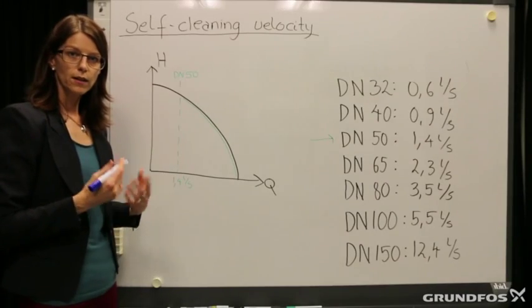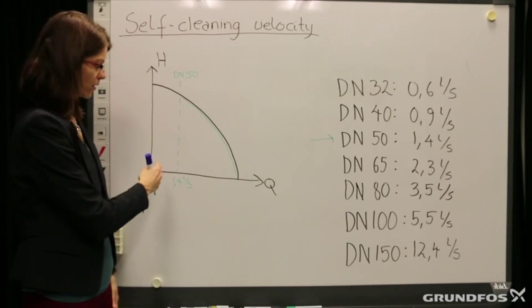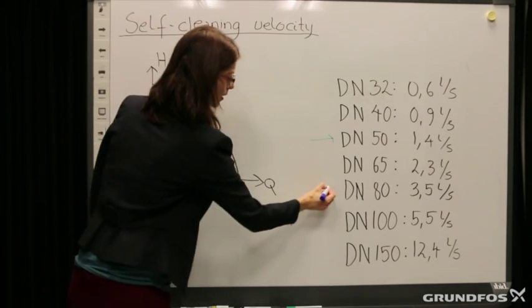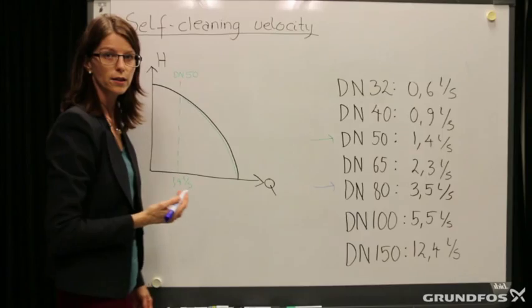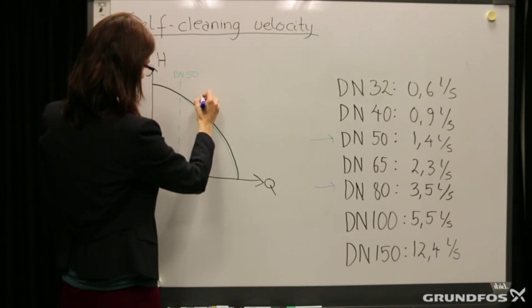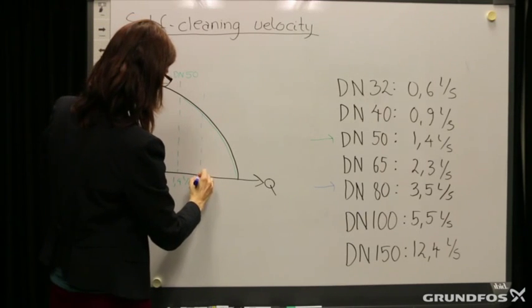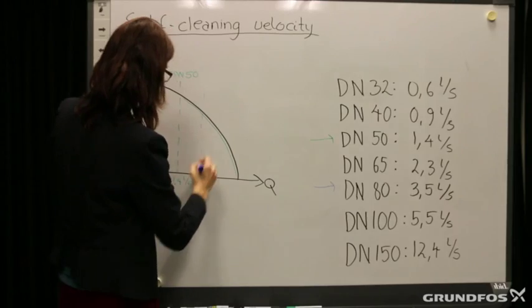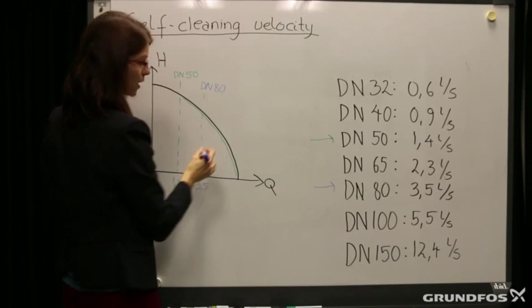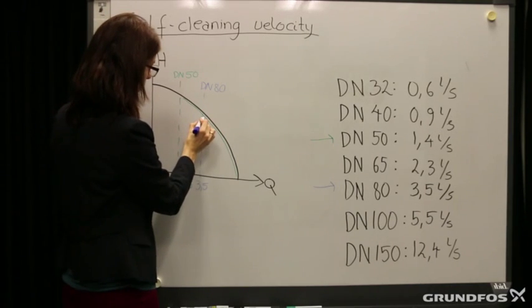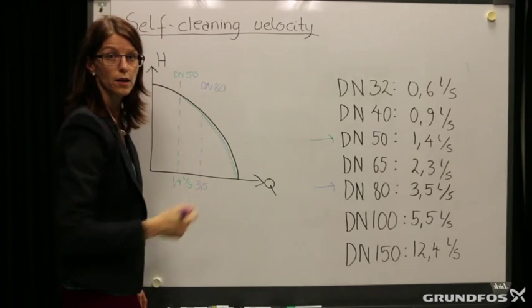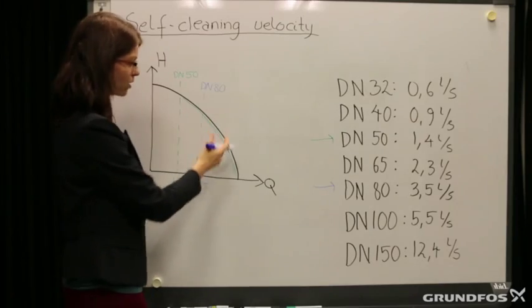The bigger the pipe size, the further to the right the borderline will move. For example, if the pipe diameter is DN80, the borderline will be further to the right at 3.5 liters per second, meaning the duty point when selecting a DN80 pipe must be in this range of the pump curve.